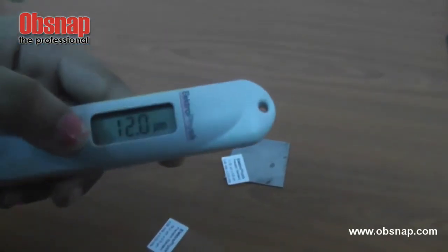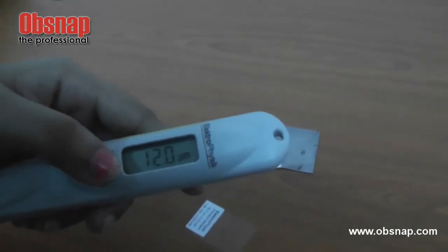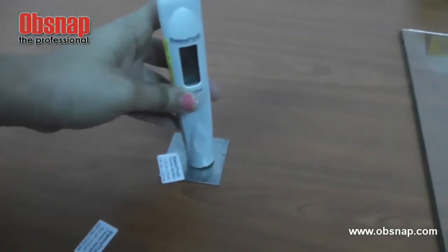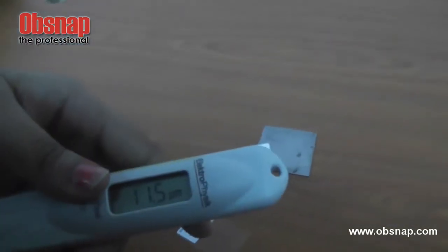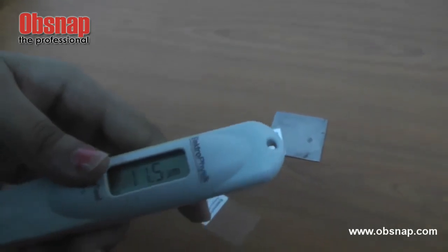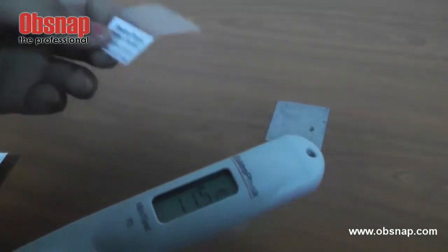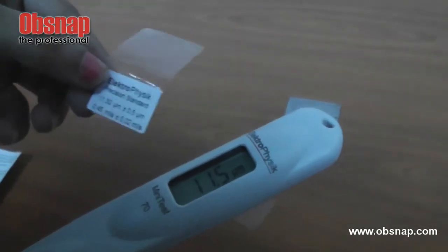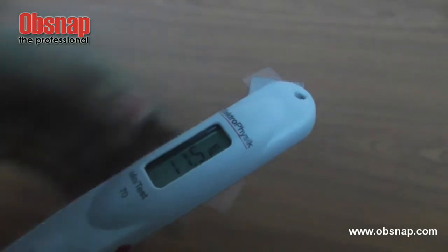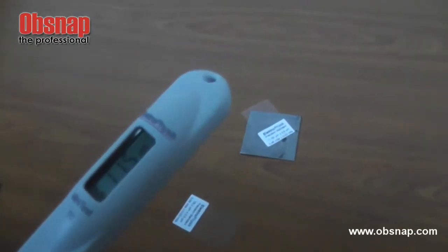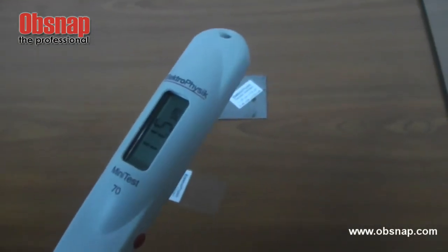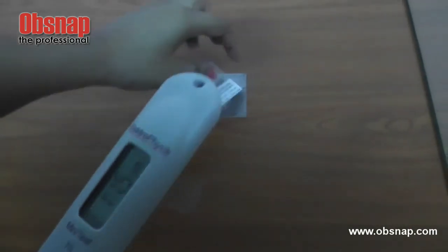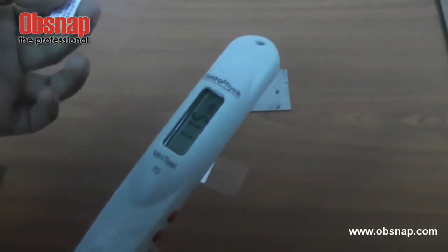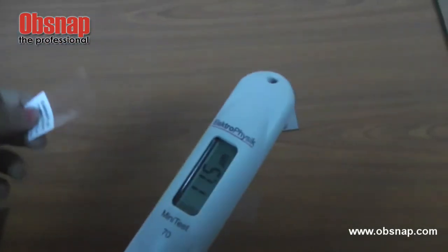Okay, which gives you a standard measurement of 12.0 micrometer. So this indicates that the displayed reading measured is the same as the standard foil measurement. This calibration has to be done when you change your sample according to the precision standard. Every measurement has to be calibrated according to the standard foil that will be measured.